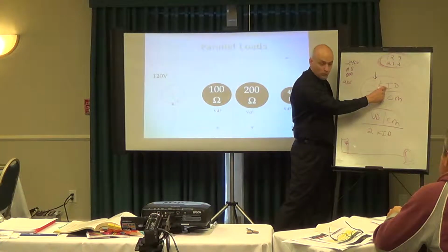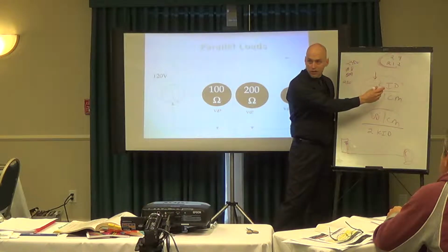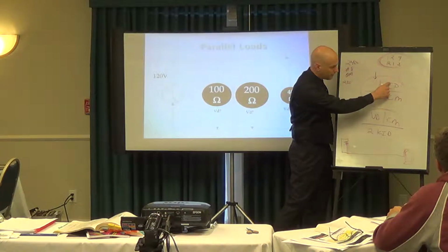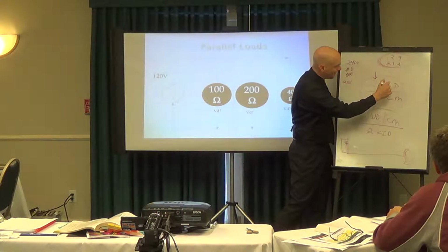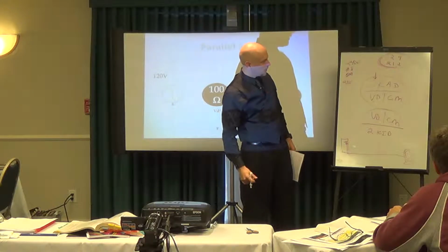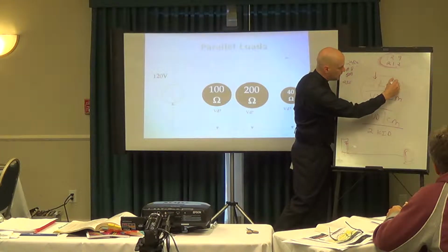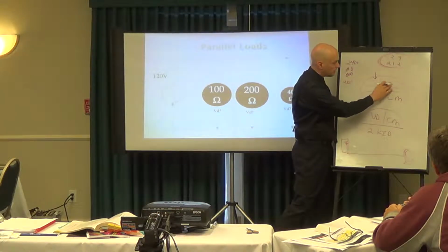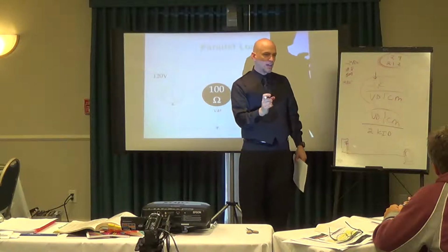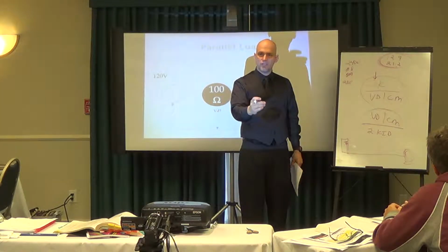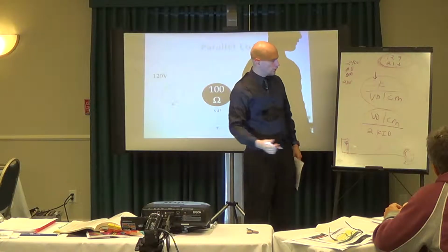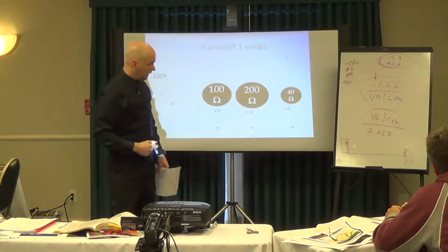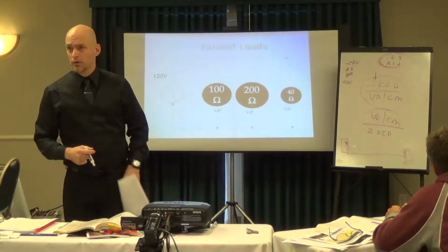The only other number we have to put up here, which instead of I, I really could look at as A, but who's ever heard of 2 cads on the block, right? You look at that as 2KAD, I suppose, and some people even look at it as 2KAL, which is length in feet instead of D for distance, but that's always in feet is the way we express this. The value we're talking about at 12.9 is ohms per 1,000 feet, not ohms per 1,000 inches or meters. So it's going to be 2KID, the D being in feet, the I being in amps, the K being the resistive value, and the 2 is there, so you can just plug in the numbers.